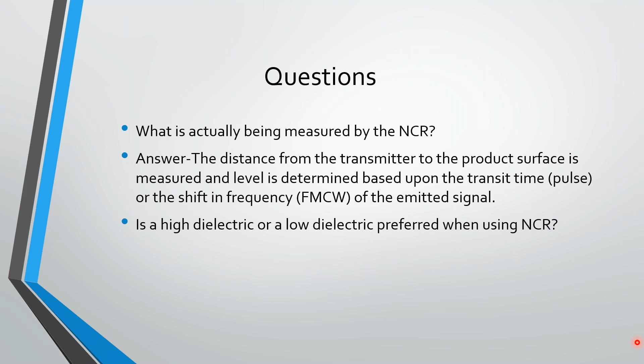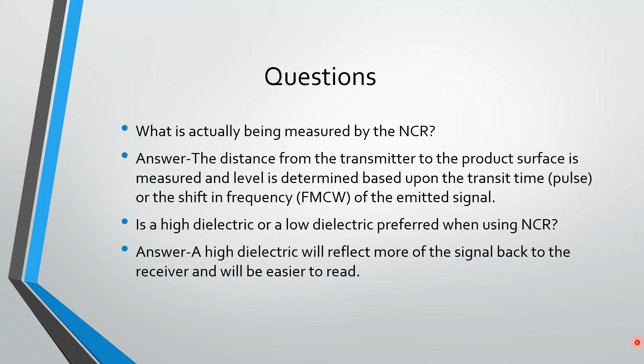Which brings us to some more questions. So what is actually being measured by the non-contact radar device? And of course, you guessed it, the same exact thing that was being measured by our guided wave: the distance from the transmitter to the product surface. That's what we're really measuring. We're looking at either a transit time pulse or a shift in frequency, depending on whether it's pulse radar or FMCW. Is a high dielectric or a low dielectric preferred when using non-contact radar? And again, same answer as we had for the guided wave radar. High dielectric will reflect more of the signal and will make it easier to read where the level is. So there's no magic there, no surprises.